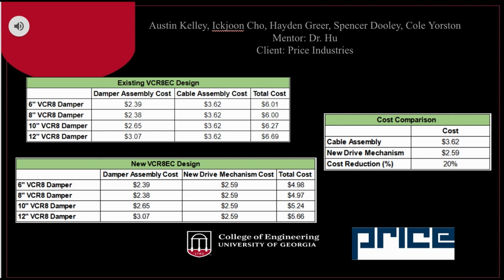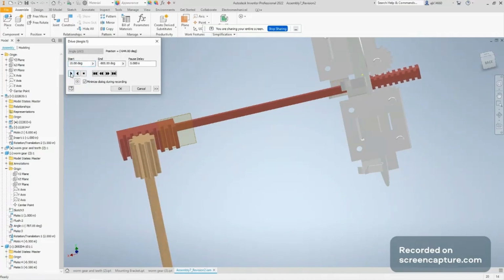The total cost of the existing VCR 8EC design ranges from $6 to $6.69. The total cost of the new VCR 8EC design ranges from $4.97 to $5.66. The price reduction from the original design to the new push-pull drive mechanism is $1.03, which is a cost reduction of 20%. Here we have included a screen share of the simulation that we had for the push and pull design, also known as Design 1. You can see that the rack and pinion solves the problem of converting rotational motion into translational motion so that the dampers may operate at full effectiveness.